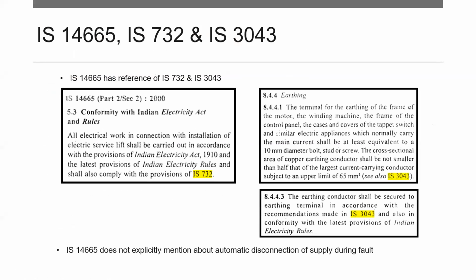As elevator professionals should be aware, today IS 14665 is still applicable, and this is an old code which is still in existence. It has a reference of IS 732 and IS 3043. But IS 732, the third version, which was given in 1989, was not based on the IEC 60364 requirements. But in the industry, somewhere around 1989-90, the ELCBs started to come into the picture. And IS 3043 is mainly covering the topics of earthing, sizing, and the connections of the earthing terminals. And IS 14665 was not explicitly mentioning automatic disconnection of the supply during a fault. So somehow this point has gone unnoticed in the elevator industry.